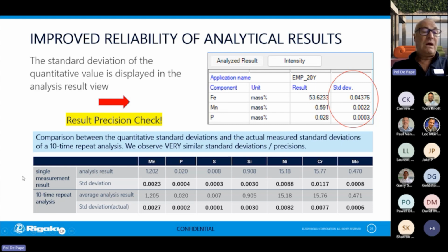If we have one single measurement, the software calculates the standard deviations, and we compare this to a 10-time repeated analysis of one and the same sample. We can see the standard deviations, look at, for example, manganese: 0.0023 in one single measurement, or 0.0027 for 10 repeatability analyses. So we can see that the standard deviation that the software calculates is really very precise.